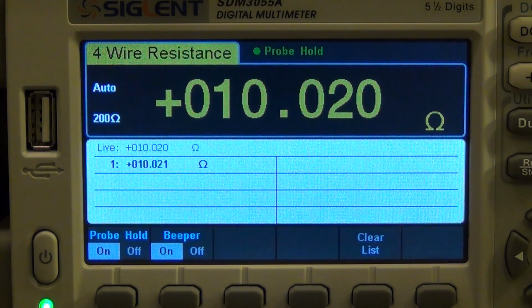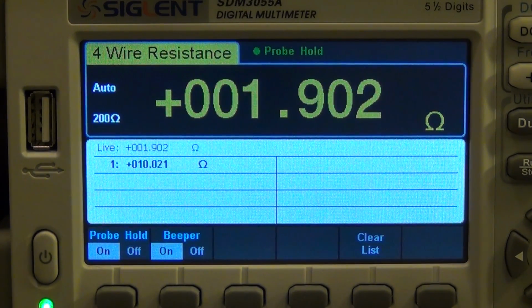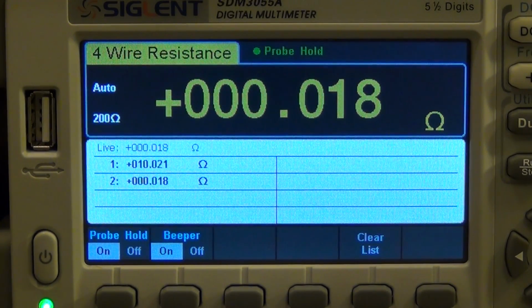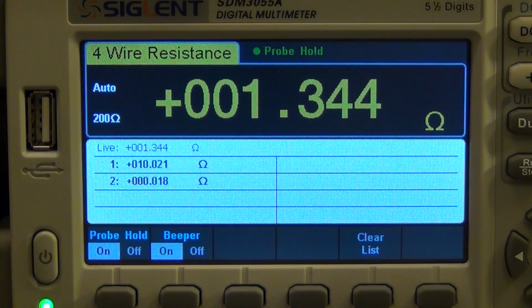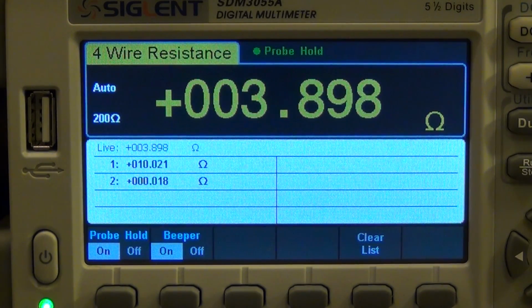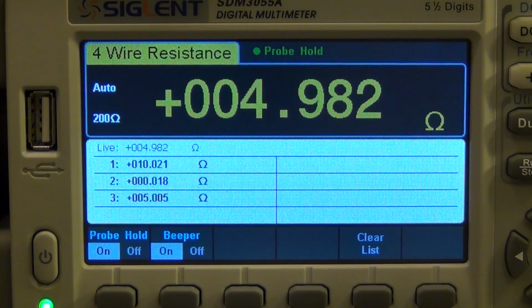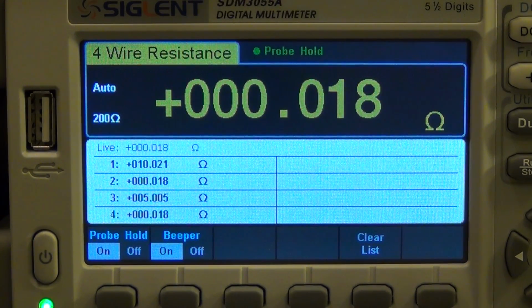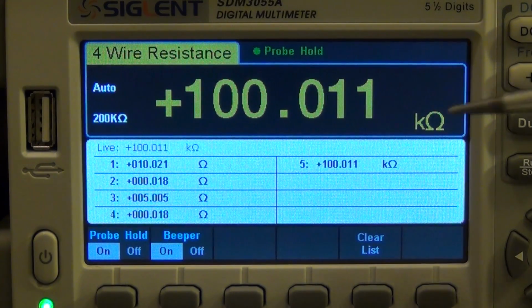And I can go give it another, let's say, go back to 0, and it measures that again. Now we are back to 0, and I can give it 1 ohm, and it misses that. See, so it doesn't consider a 1 ohm addition as a new measurement. So I can dial in another 1 ohm, and nothing. The change is simply, oh, there you go, it just picked it up. So once it crossed the 5 ohm difference from the original measurement, it counted it as a new measurement. I can go back to 0, and it counts it again. So it depends on how much measurement variation there is, and I can make a really large measurement. Here's a 100 kilo ohm difference. There it is, and it added it over there.